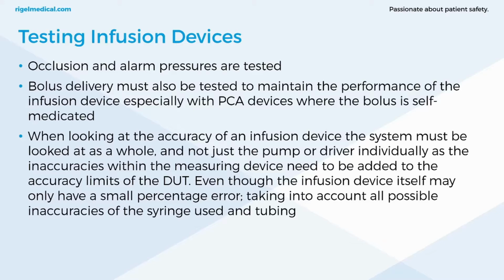We've got to remember that the infusion device needs to overcome pressures within circuits, and it's the whole circuit as a whole that needs to be tested, much like in many calibration procedures, that the whole system is to be tested, not just the device on its own. So even though the infusion device itself may only have a small percentage error, taking into account all possible inaccuracies such as the syringe used and also the tubing.